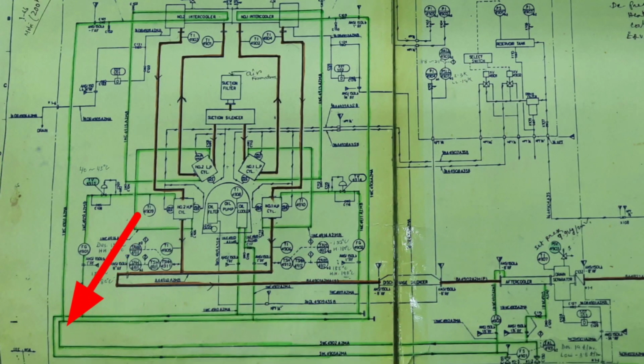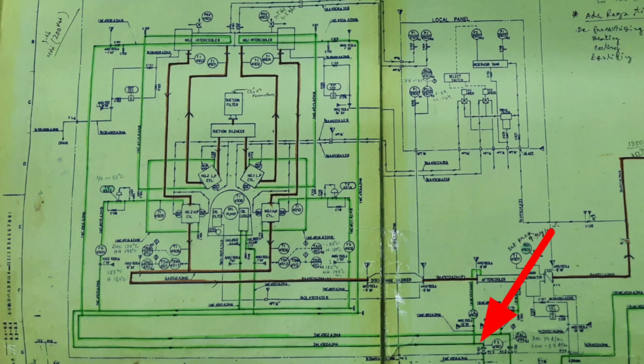So the inlet cooling water comes by this line and goes to the number 2 intercooler, and it will come out this way and go to the number 2 LP cylinder, and after that to the number 2 HP cylinder, and it will come out by this control valve, and there is FG, and finally it will discharge to the cooling tower system.